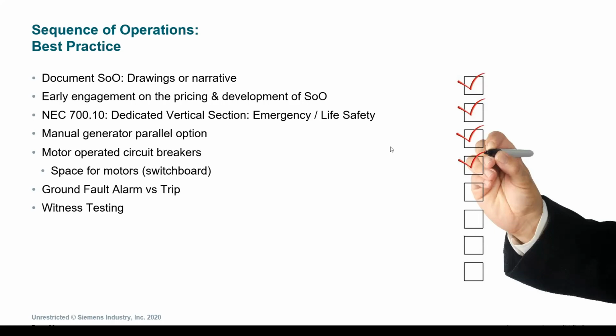One opportunity for doing this is the witness testing. And this is something that is added into the specifications for that parallel switchgear. It allows the engineer, yourselves, the contractor, and the end user to go to the manufacturing facility prior to arrival on site and review all of the sequence of operation, all of the failure modes, and make any adjustments that may be identified or have been missed prior to the demonstration.